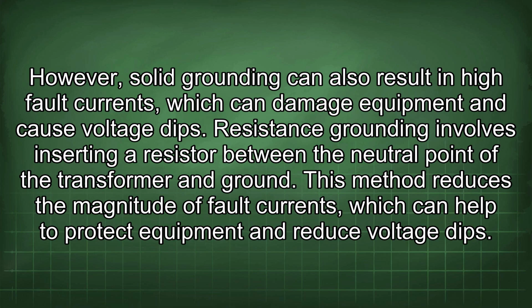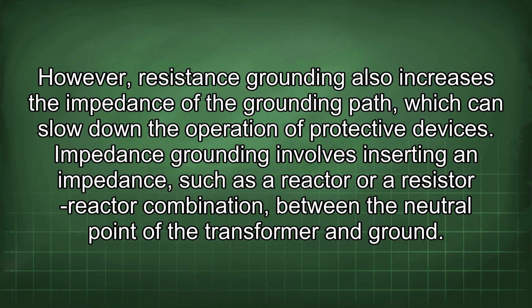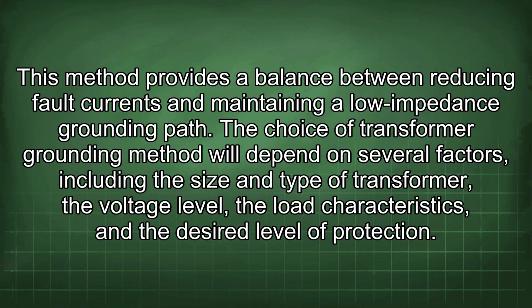Resistance grounding involves inserting a resistor between the neutral point of the transformer and ground. This method reduces the magnitude of fault currents, which can help to protect equipment and reduce voltage dips. However, resistance grounding also increases the impedance of the grounding path, which can slow down the operation of protective devices. Impedance grounding involves inserting an impedance, such as a reactor or a resistor-reactor combination, between the neutral point of the transformer and ground. This method provides a balance between reducing fault currents and maintaining a low impedance grounding path.